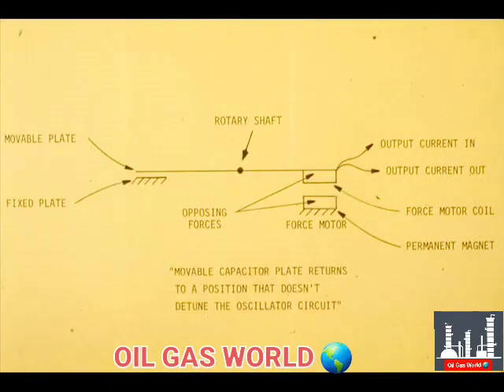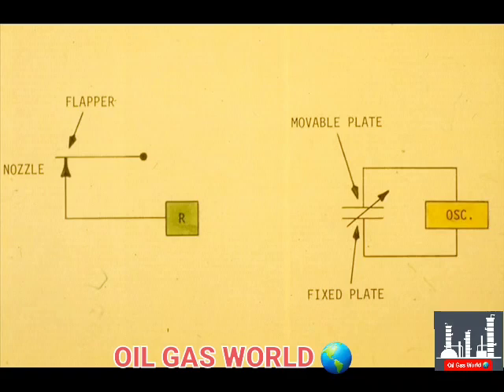This negative feedback action restores the movable capacitor plate to a position that doesn't detune the oscillator circuit. The variable capacitor can be compared to a flapper nozzle. The flapper nozzle must be restored to throttling position. The variable capacitor must also be restored to a position that doesn't detune the oscillator circuit.